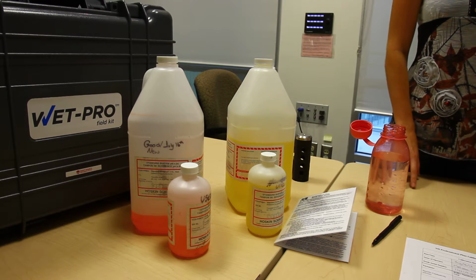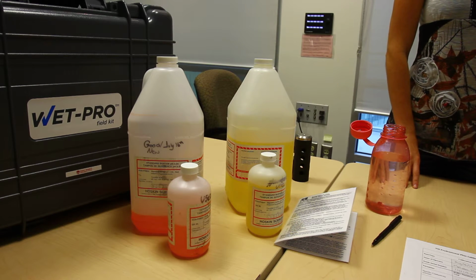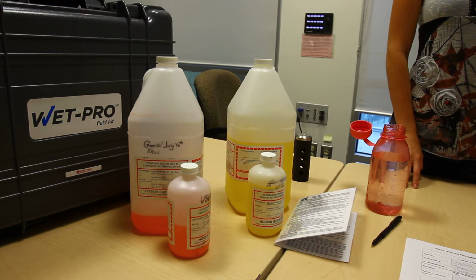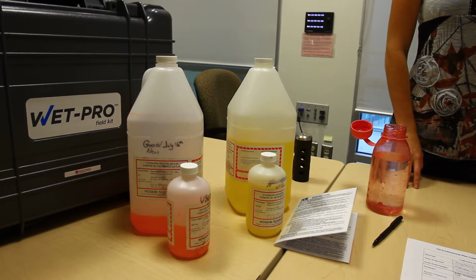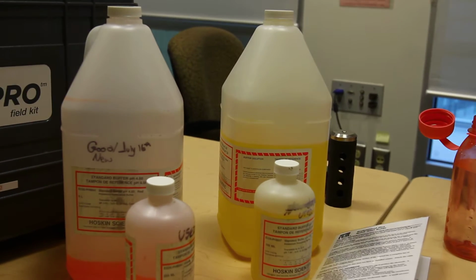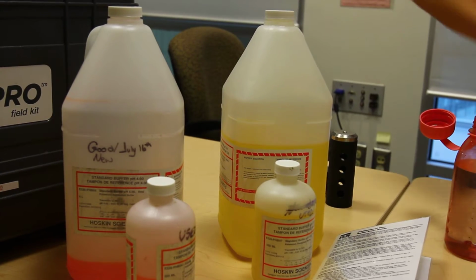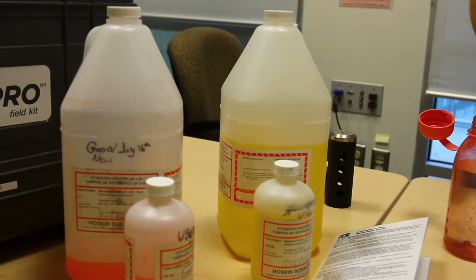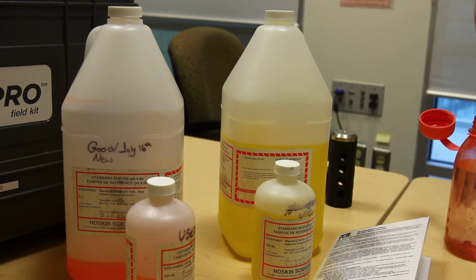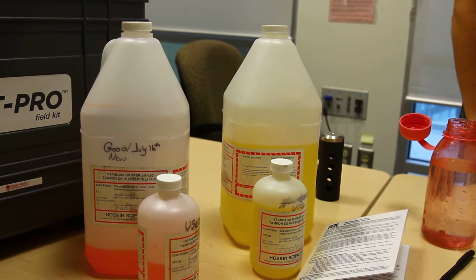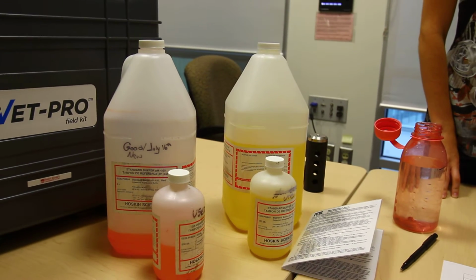You have just finished rinsing with tap water, and now we will begin calibrating for pH. For freshwater monitoring, it's recommended to calibrate with a buffer 4 and 7 solution, and if you're in brackish environments, you can also use a buffer 10. There is an auto buffer recognition to determine which buffer value the sensor is in, and it will allow up to 6 points of calibration.